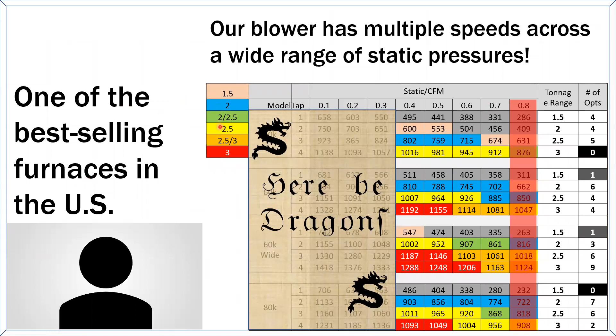And so if you need 525 CFM, why would you need 525? I thought you were doing 400 CFM per ton. Well, if the latent load is going up, you better slow your air down. More air. We used to think of more air as a good thing. Now, well, more air reduces the moisture removal capabilities of your unit. I want less air. I want exactly the amount of air that I want to have. And of all the furnaces available from this family of equipment, from this brand, there are only 3 capable of it. And on 2 of them, there's only 1 static pressure and 1 fan speed where I can even get close to this. That's a problem, right?